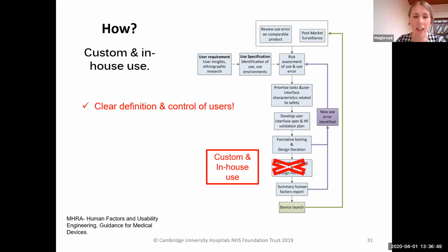And then just a note that within custom and in-house use, human factors is really valuable and much easier to do than if you were looking at a CE mark device. The reason for that is, especially with custom devices, you have one user, so it's very easy to define what your user requirements are and what your user need is, because you're designing for a particular user.